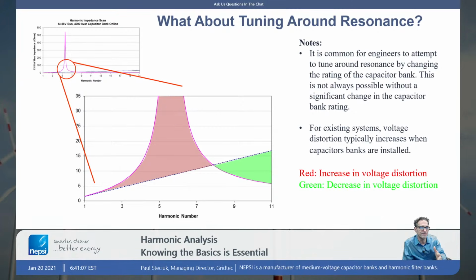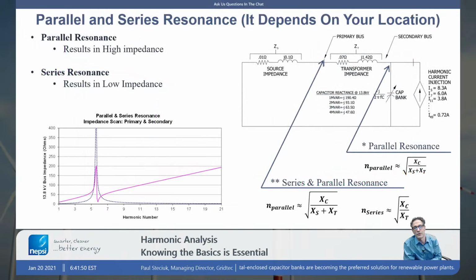We all have a feeling for the resistance of a cable per meter. The transformer impedance, oftentimes we do not know. It's not on the nameplate, so it's something that is unknown. Because resistance is not known, and the impact of harmonics on skin effect and on proximity effects, we know there's some effect, but it's hard to know exactly how much that is. So the width of that impedance curve is also not known. And of course, you've got the possibility of shift due to changing system conditions. So tuning around resonance is something that we would not typically recommend, and we actually don't think it works very well.